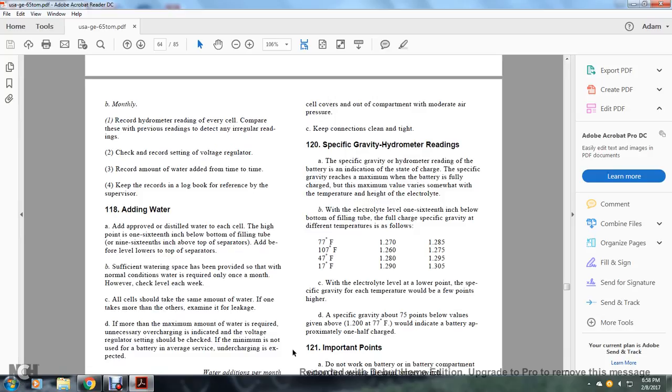Specific gravity hydrometer readings: The specific gravity of hydrometer readings indicates the state of charge of the battery. The specific gravity reaches maximum when the battery is fully charged. The maximum value varies somewhat with temperature and height of the electrolyte.